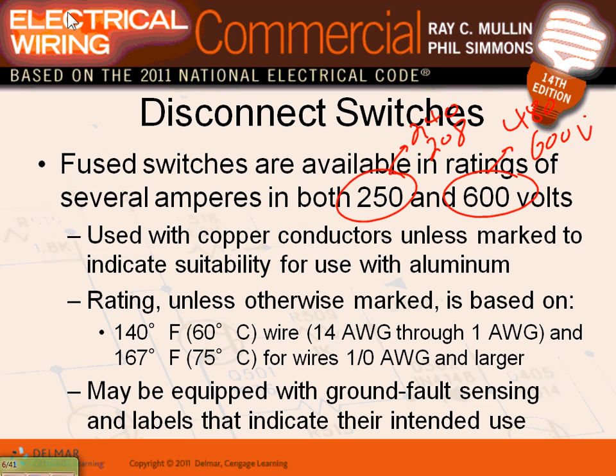If your system is 600, or 480, what do you need? You need a fuse that's rated for 600 volt. And oh, by the way, a 600 volt rated fuse cannot fit on a 250 volt rated fuse holder. They don't fit. The last thing you want to do is put a 250 rated fuse in a 600. It's not rated. It will arc and spark because the insulation, everything, is not rated for that stress of voltage. So it's a big deal, guys, in terms of voltages.